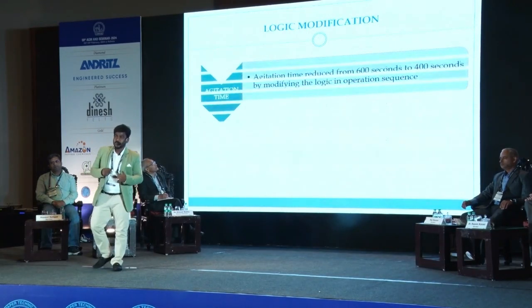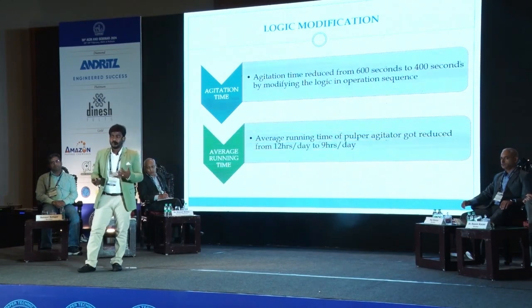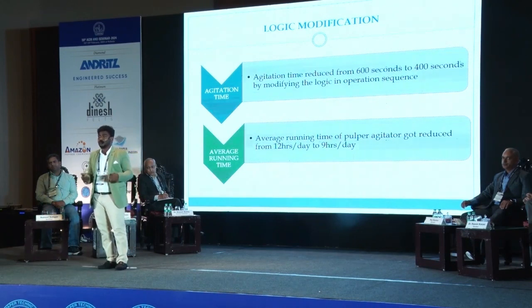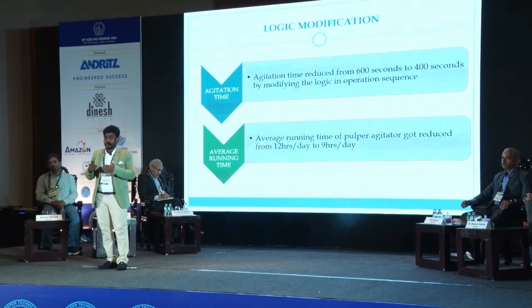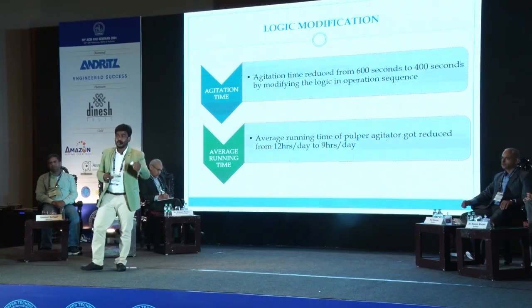So we discussed with the instrument team and we studied, and after finding the fact that 600 seconds of agitation would not be required for slushing the loose broke, we decided to reduce the time in the logic. So we approached the instrument team and we reduced the agitation time in the logic from 600 seconds to 400 seconds for these two pulpers.